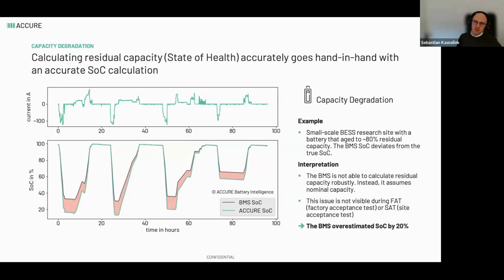The BMS just assumed nominal capacity, 100%. As you can imagine, you're operating your battery over a 10, 15, 20-year time frame, and battery engineers building those systems will test the battery with just a few hundred cycles in the lab, and then everything gets extrapolated from this. Based on that, you get the results in your BMS — lookup tables and so on that account for these aging effects.